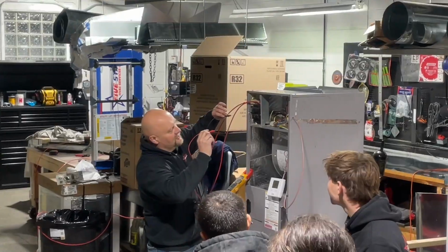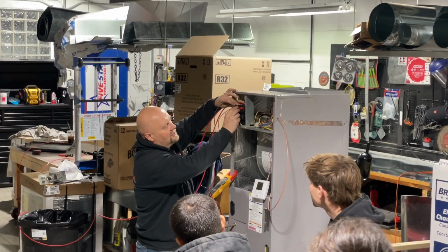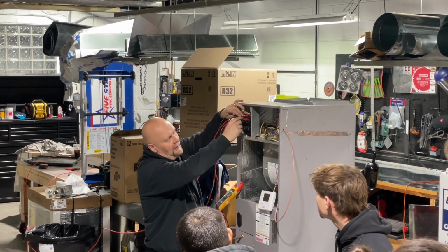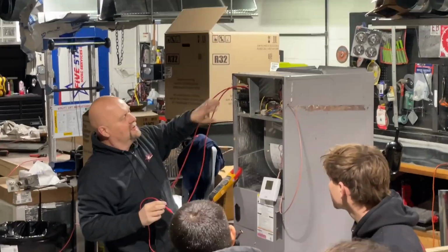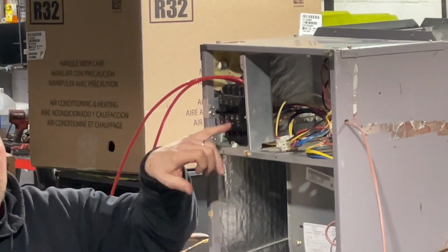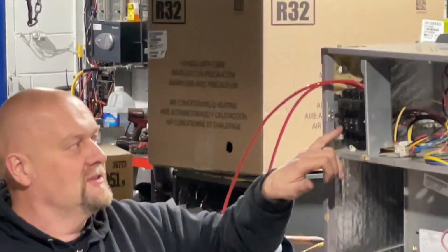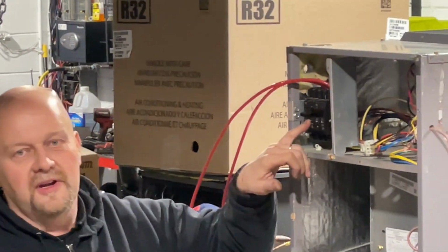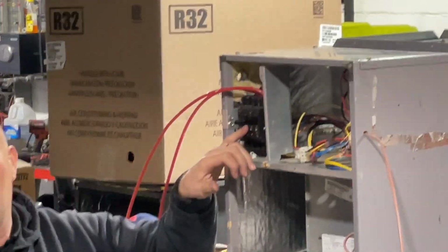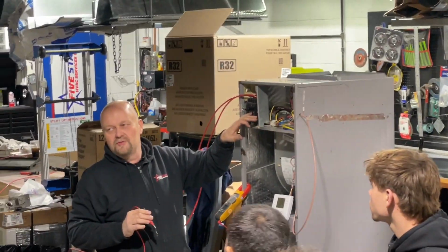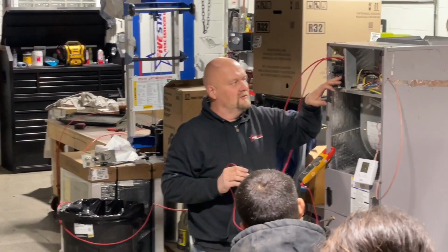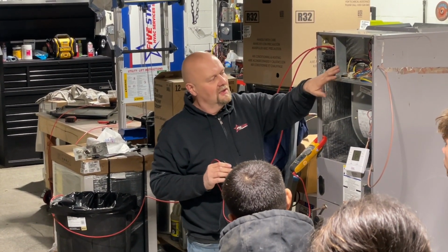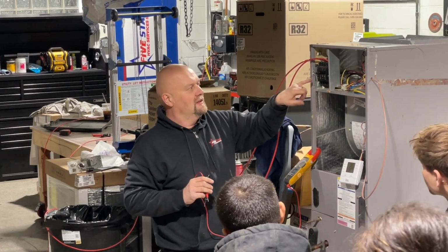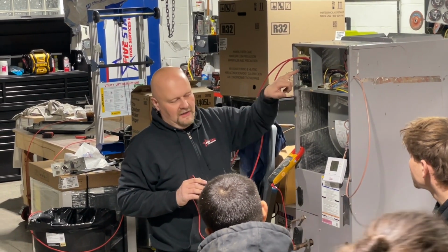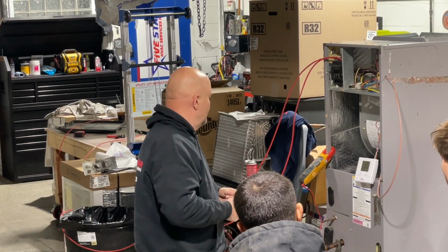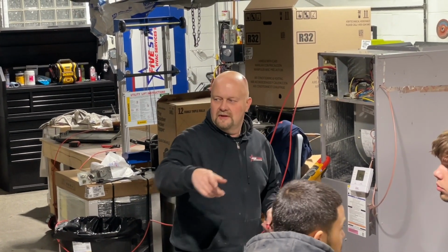So first thing I always want to do is make sure we have 240 volts at our power port coming in. Every single time you're going to see a circuit breaker on an electric furnace that's mounted onto the furnace itself, sometimes you're going to see two of them. Typically the second circuit breaker is the one that's extra power for the second stage. So most furnaces will have two stages. The second circuit breaker doesn't take any part in controls, blower, or any actions other than it supplies power to another circuit. So back here we had, Paul, where was the electric?